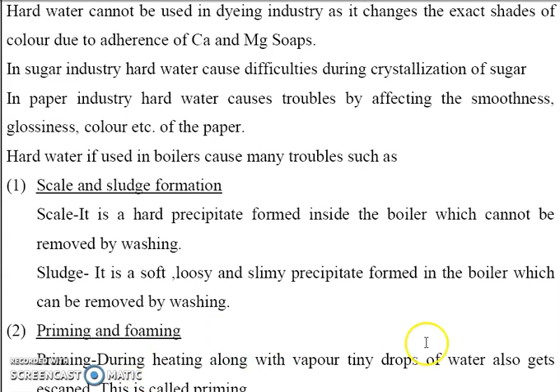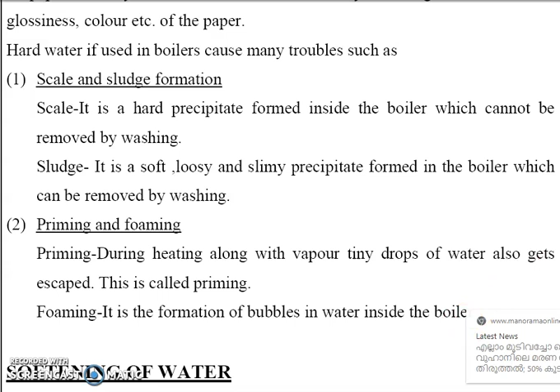Priming and foaming also occur in the boiler. On continuous evaporation of hard water in the boiler, some tiny drops of water are carried along with the steam. That wet steam formation is known as priming. Foaming means persistent bubble formation inside the boiler. This priming and foaming also leads to decreased thermal efficiency and wastage of fuel.